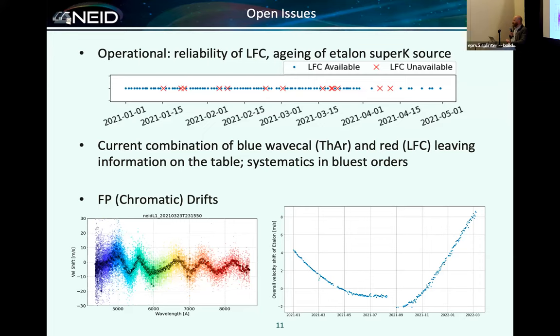August 21 summer shutdown. So we burned through one PCF and we swapped to a spare supercontinuum laser. And after that, it behaved differently. And we did this again last summer, and after that, it behaved differently. So we're still trying to understand this, but these high-powered supercontinuum sources are not so trivial to use.